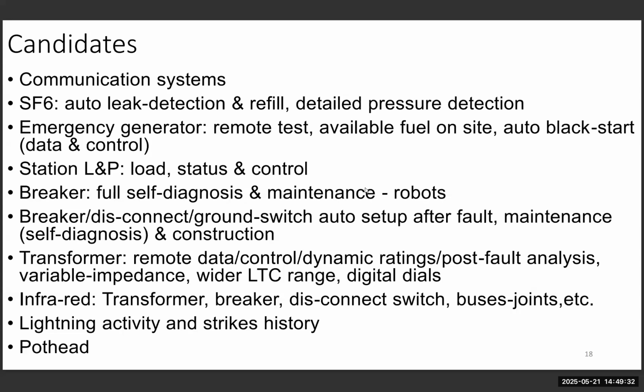Now, the breakers. One thing that we didn't discuss a lot is the inspection cycle. Equipment has different inspection cycles. They have a visual inspection cycle, they have a testing inspection cycle, and they usually have a longer-duration cycle where they take the equipment apart into pieces and put it right back. It's almost like taking your car for a full tune-up, where they check everything and make the necessary changes. That is usually the last one. The latest breaker technology is able to skip a lot of this inspection because number one, they are always monitoring the flow of power, and they always measure when a fault happens and the breaker operates. You're able to know from the way it operated whether it requires additional maintenance or not. By relying on all these tools, which are usually self-diagnosing, and most of them, at least from a pilot perspective, are available. Again, that's a very important point.